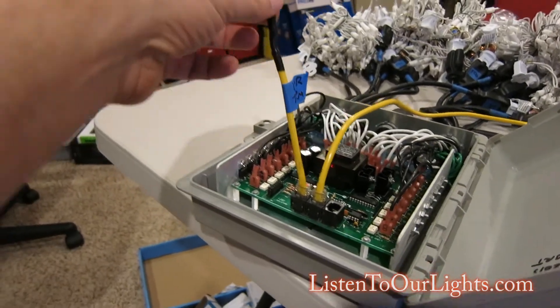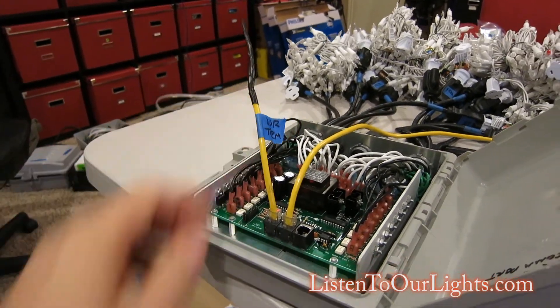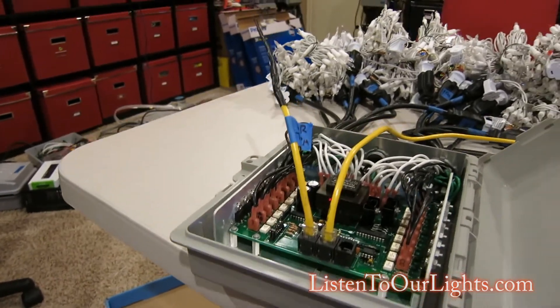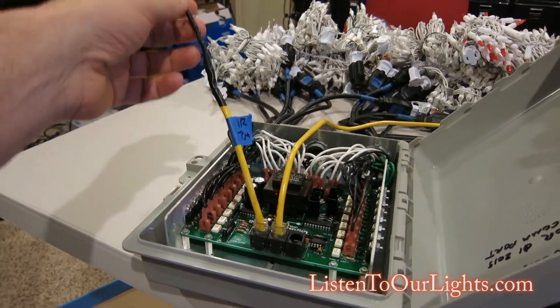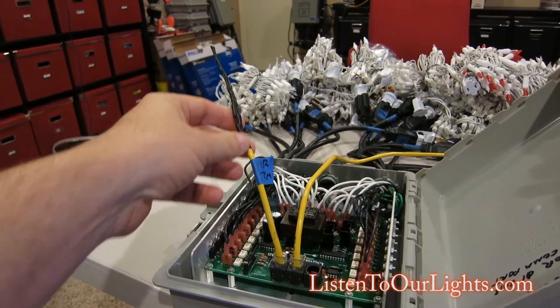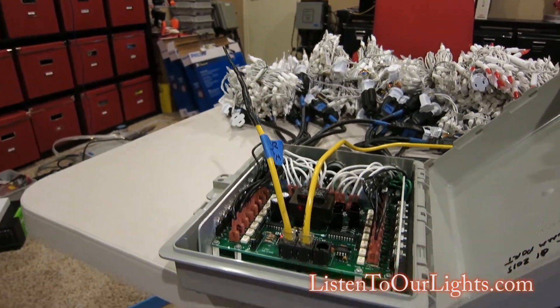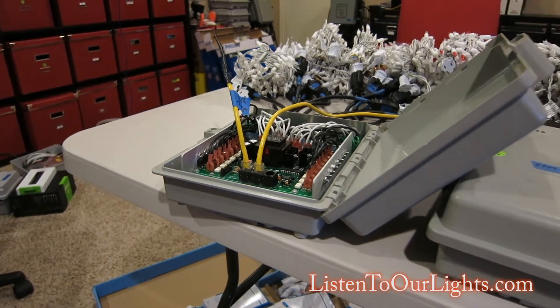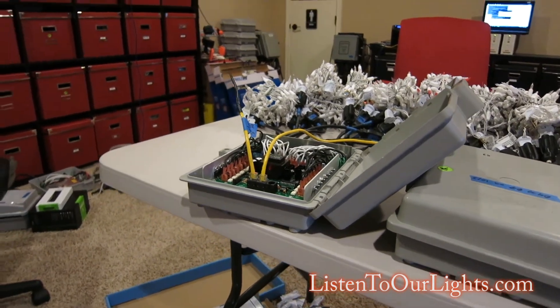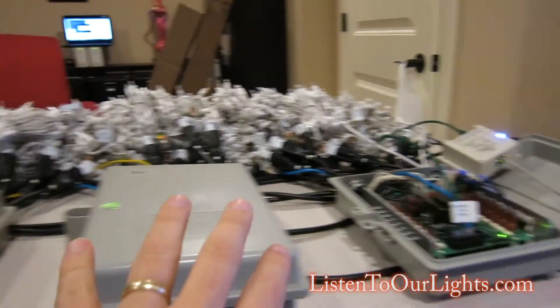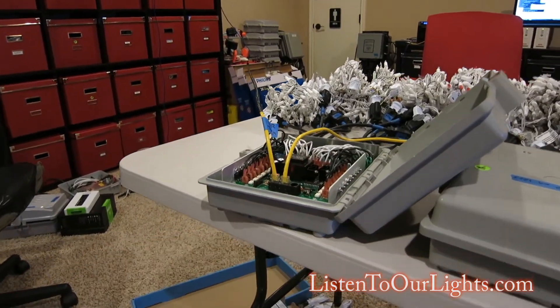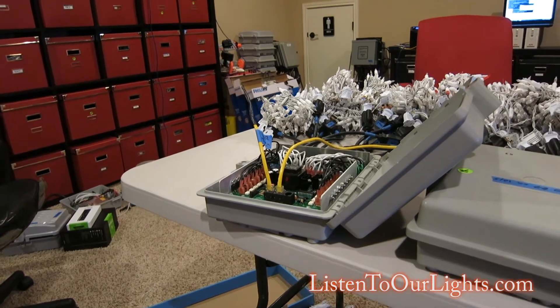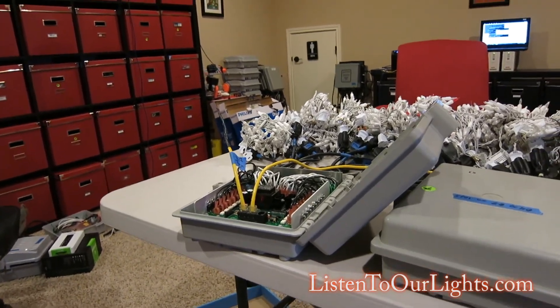The other thing that's a little different is down here on the end of the chain, I've made a Terminator. So an RS-485 Terminator, simply, you just jumper the pins with a 120-ohm resistor. And I have a separate video on how to make those. Those are also very easy to do. And the purpose of that is as the signal gets passed down the daisy chain, when it gets to the very end, to the Terminator, it'll absorb any residual signal, so it doesn't bounce back and cause problems.